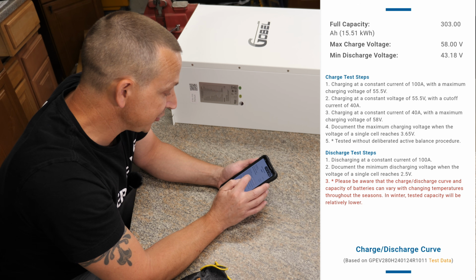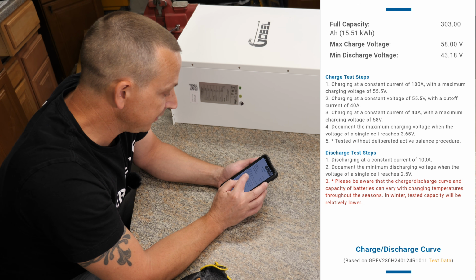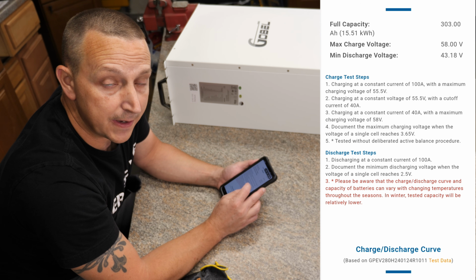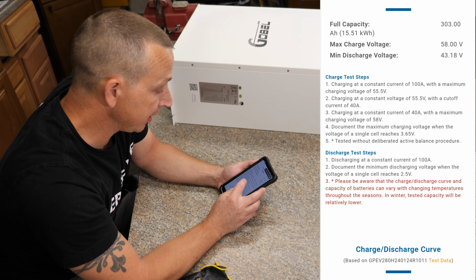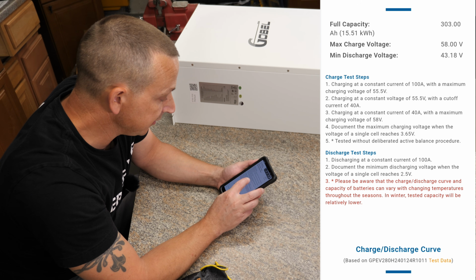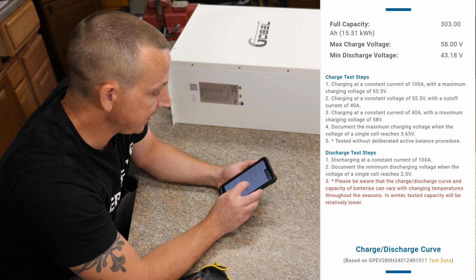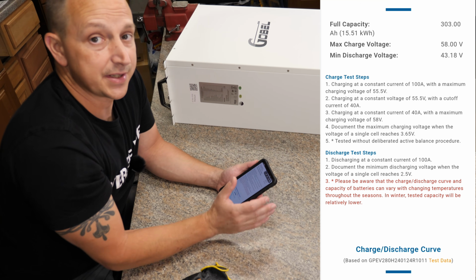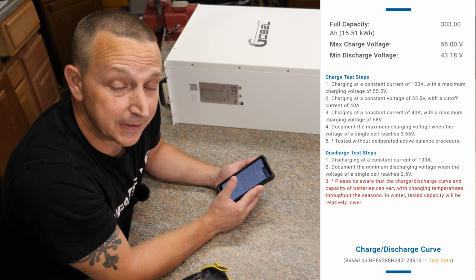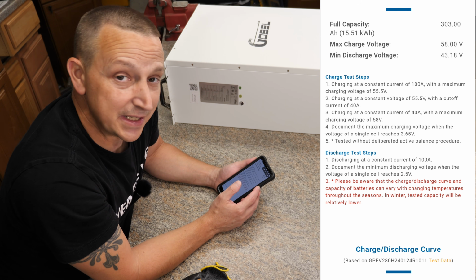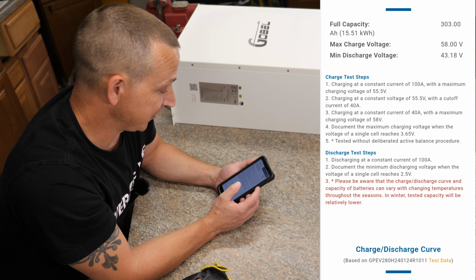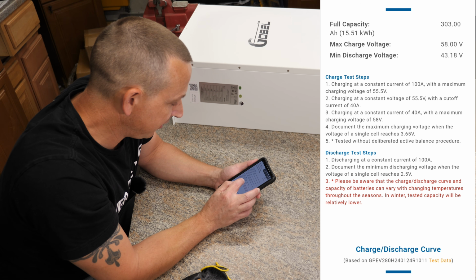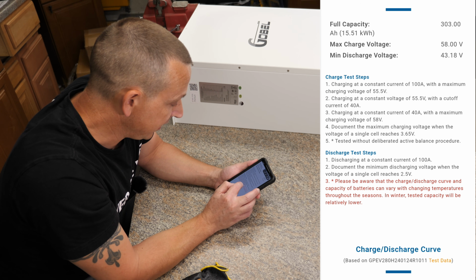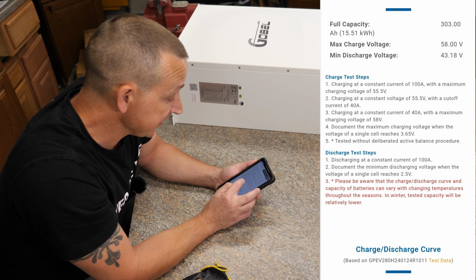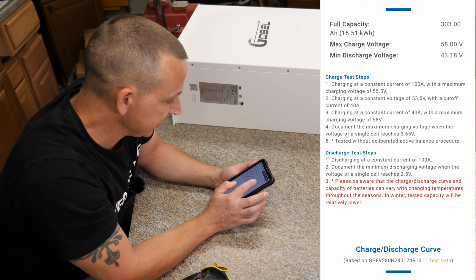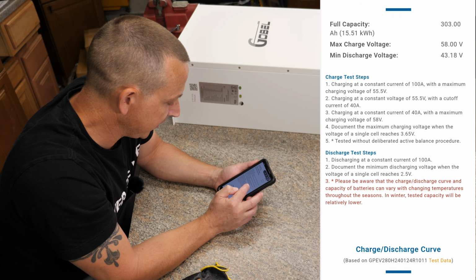And then of course they have their charge steps and discharge steps right here. So basically what they did is they went to 55.5 and held it there for a while, and then after that they went up to 58 volts, and basically whenever the first cell reached 3.65, they've gone through and matched the cells so good that they were able to charge it up to 58 volts. Which means that most cells are at that 3.6 volt range. Anyway, discharge test steps are discharging at a consistent current of 100 amps. Document the minimum discharge voltage when the voltage of a single cell reaches 2.5 volts. And that's where they were able to get down to 43.18.